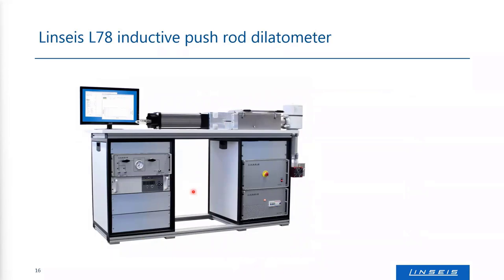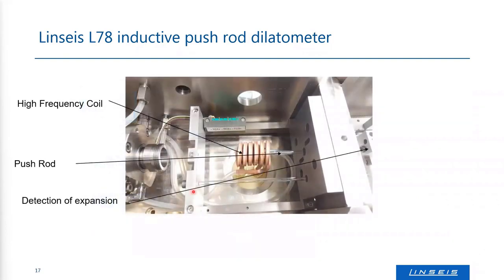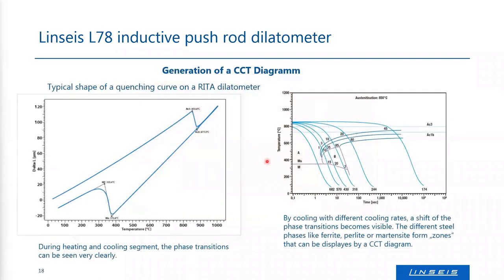We also have special inductive pushrod dilatometers in our product range. The heating is done with a copper coil, illustrated in the photograph, which heats the sample inductively around the pushrod and sample. This can be done for metals, steel, and other alloys. The purpose is to heat up very quickly and also cool down quickly, at rates of hundreds or even thousands of Kelvin per second, to generate phase diagrams and CCT diagrams for steels and other metals.